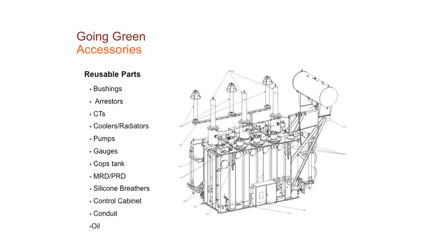A lot of these items, such as the coolers and the pumps, can also be repaired as well. So if you decided that you don't want to replace them, we can refurbish them with our factory and reuse them. The relief devices, COPS tanks, silicone breathers, control cabinets, the conduit for the transformer, control boxes, and the oil as well.